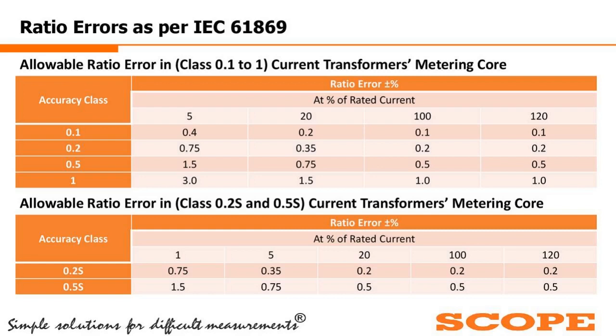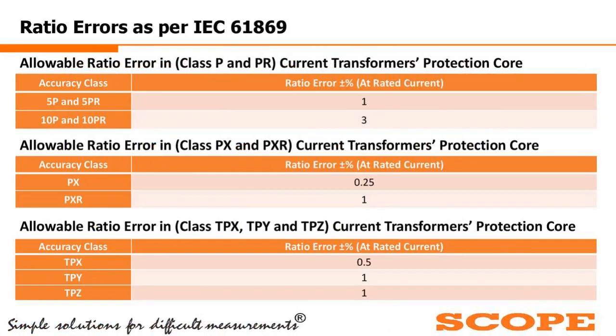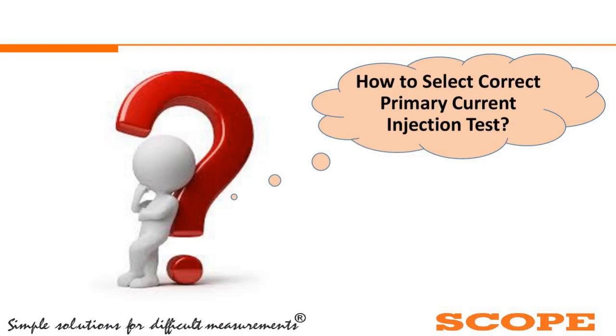For protection cores — class P and PR — the limits are: for 5P and 5PR, ratio error should be within 1%; for 10P and 10PR, the ratio error should be within 3%. For special protection cores PX and PXR, the ratio error should be within the specified limit. For transient protection cores — TPX, TPY, and TPZ — the limits are: TPX 0.5%, TPY 1%, and TPZ 1%.